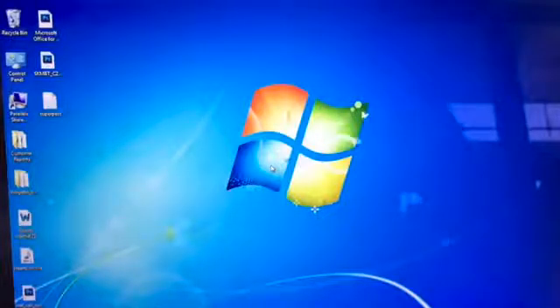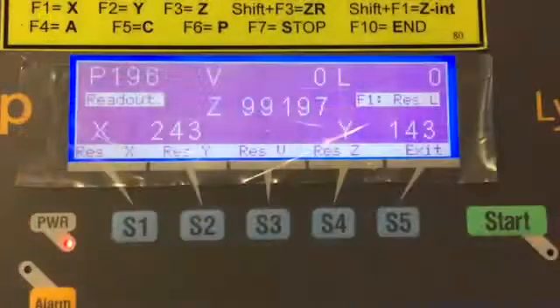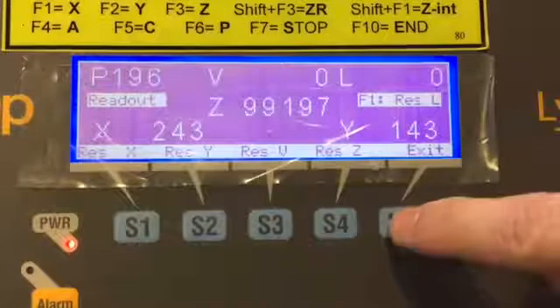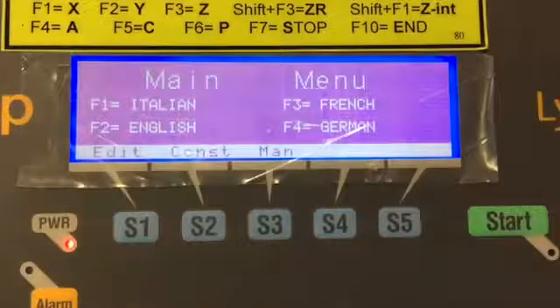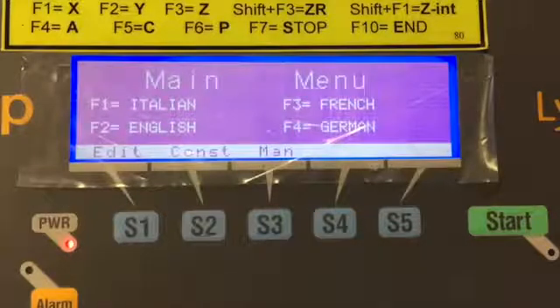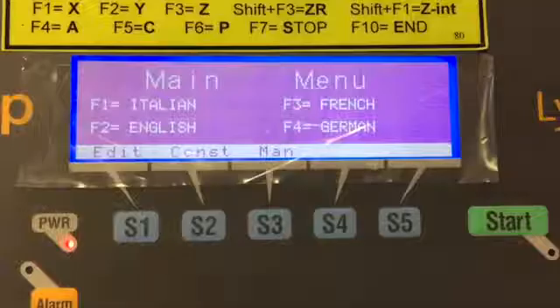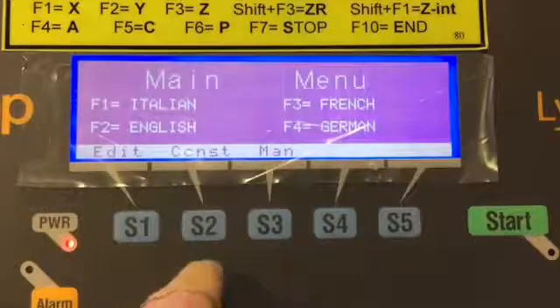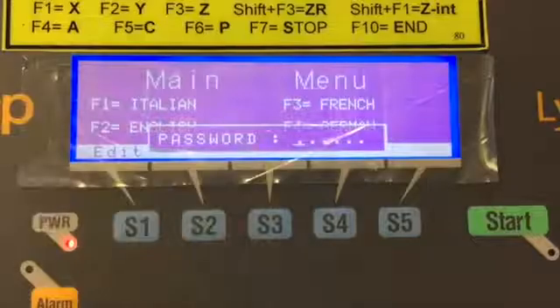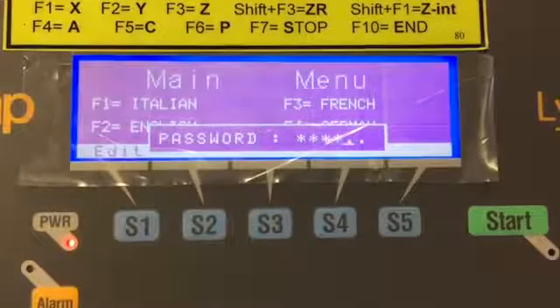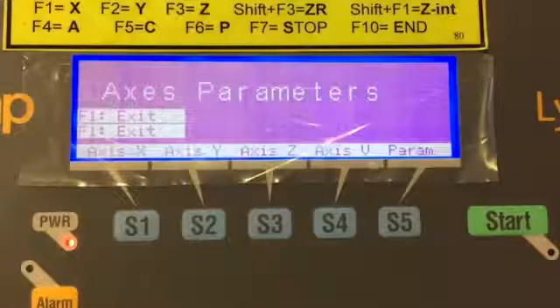Continue on with loading the parameters of your machine back into the control. To reload the parameters for the encoders you're going to exit out of the main menu or the manual menu. You're going to go back to the main menu. From here if you want you can put it in the language of your choice. If we want English we want F2. So we push F2 and that puts it in English for us. Then we press the constant button and we enter the password. 300346 is the password.